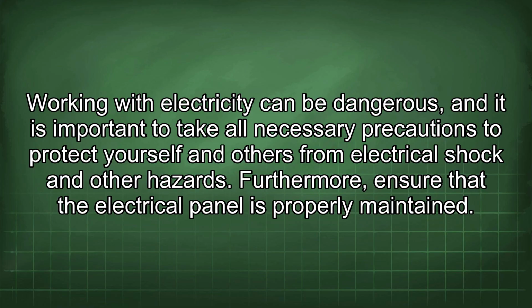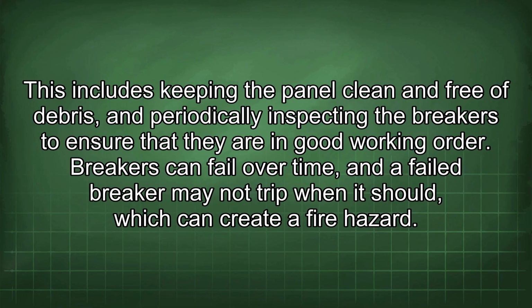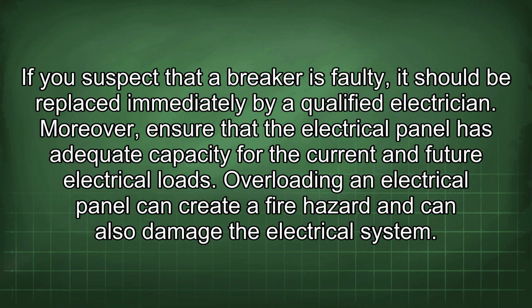Furthermore, ensure that the electrical panel is properly maintained. This includes keeping the panel clean and free of debris, and periodically inspecting the breakers to ensure that they are in good working order. Breakers can fail over time, and a failed breaker may not trip when it should, which can create a fire hazard. If you suspect that a breaker is faulty, it should be replaced immediately by a qualified electrician.